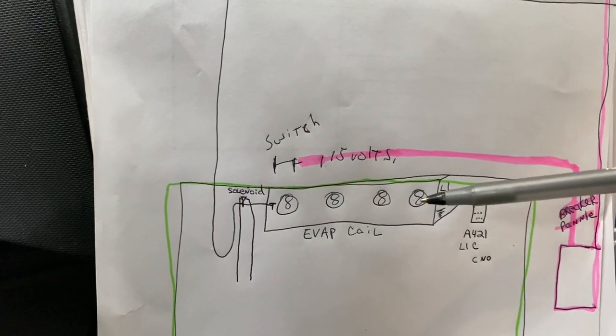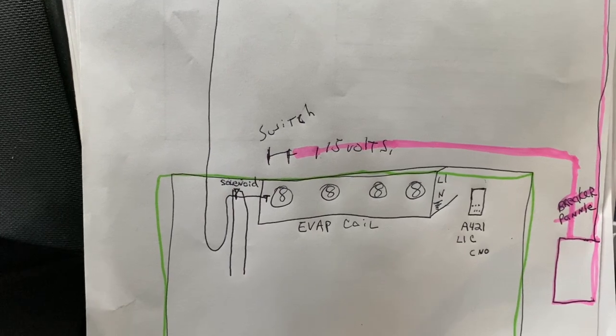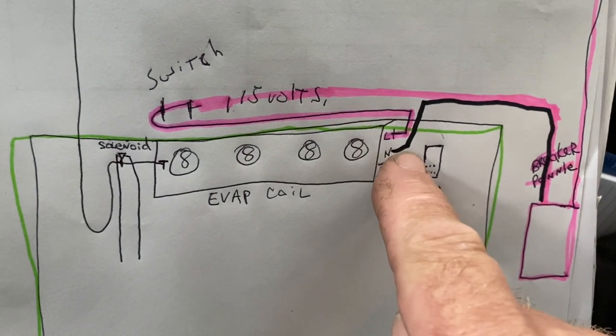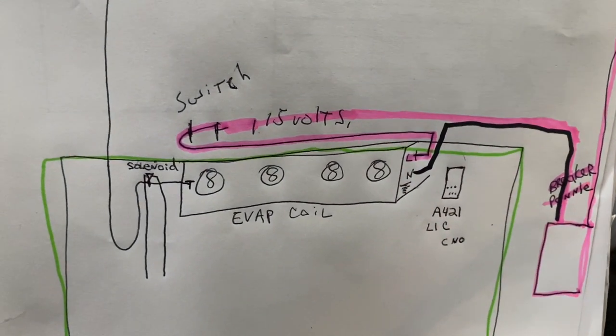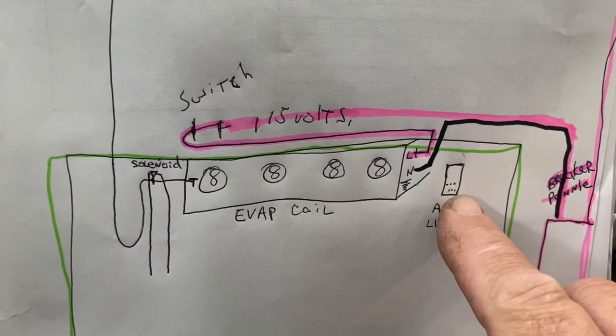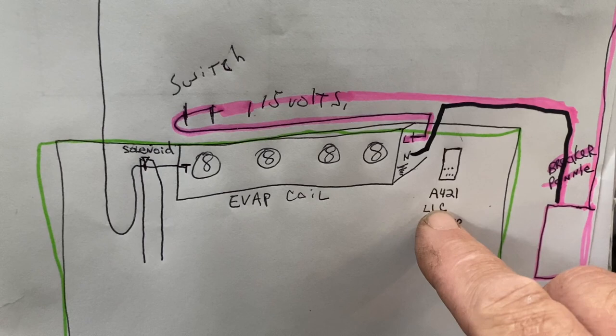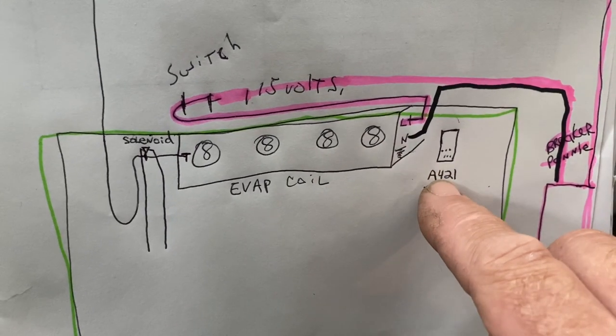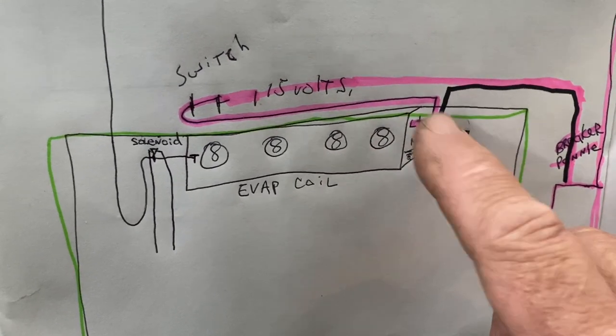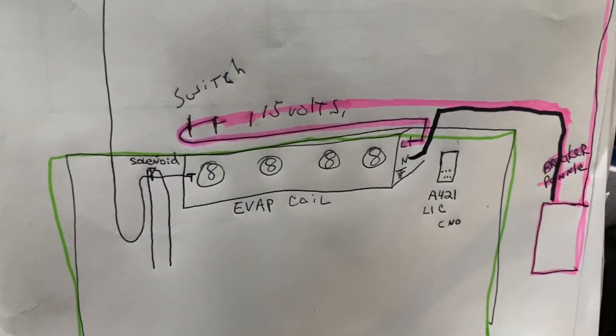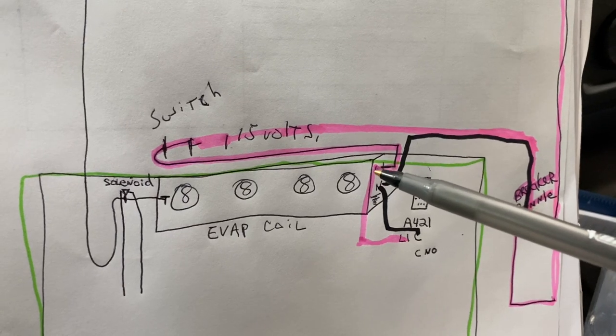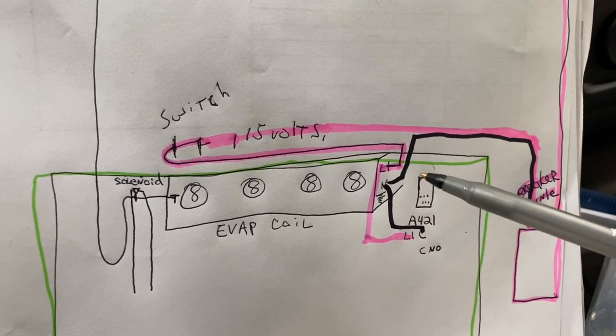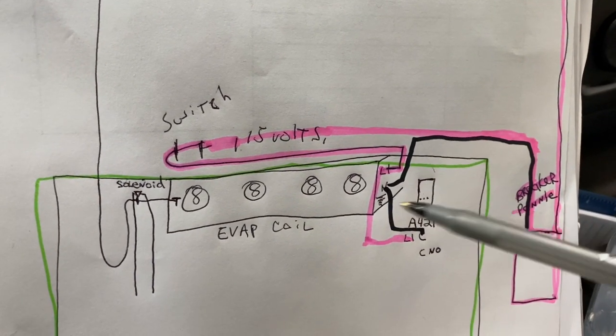And those fans are going to run 24-7. We went ahead and we fired up the fans. We got our L1, neutral goes back to the neutral. Now we've got to fire up, we've got to get power to our A421, which we're going to take from L1 and neutral, and we're going to take those to fire off our thermostat. We need power to power up our thermostat. So we got L1 and we got Common just to get power to fire off our thermostat. So now our thermostat is going to have power. Our fans are running.